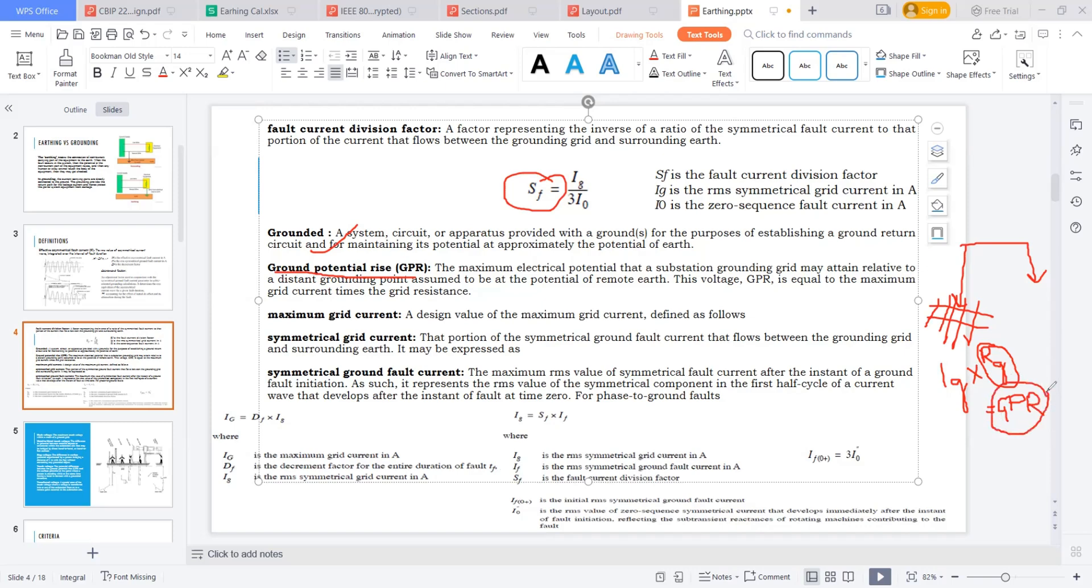This voltage is a concept of how much voltage is raised here relative to remote earth. Suppose the potential here is 0 volts and the potential here is 2400 volts. My GPR is 2400 volts with respect to 0 volts. Generally voltage is calculated from high potential to low potential. Similarly, the maximum electrical potential the substation grounding grid may attain relative to the distant grounding point is GPR. Generally, GPR equals grid current times grid resistance.